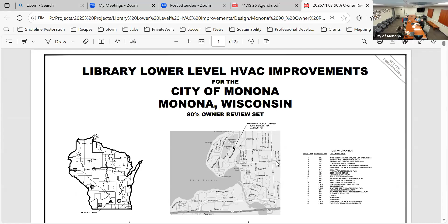So, 90% plan review, just as a general summary: the lower level library HVAC system is getting completely replaced, outside of a majority of the ductwork. A lot of the ductwork is going to stay in place, but there are two new boilers, a redundant system, two separate pumping systems, two air handlers, because we have to fit the air handlers on the ductwork that exists there now, and it comes through the slab and the floor. So we have to set the air handlers back on top of where those locations are — that's our limiting factor in the room. All new electrical.